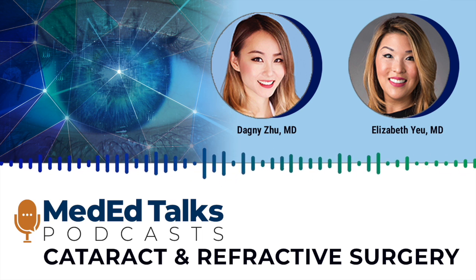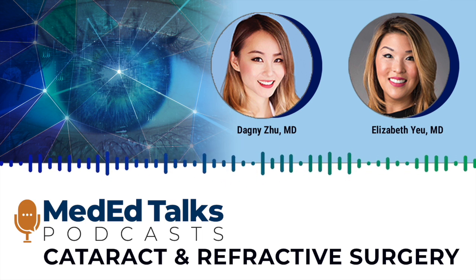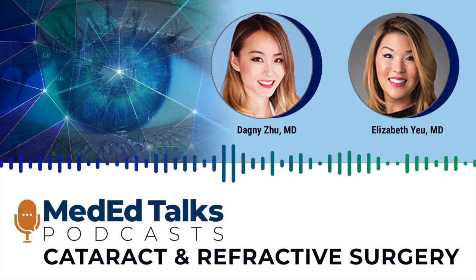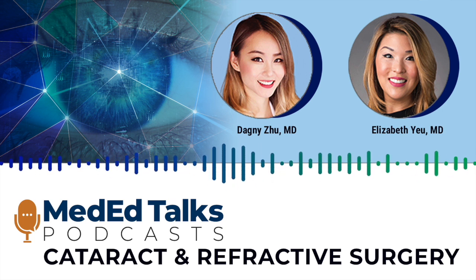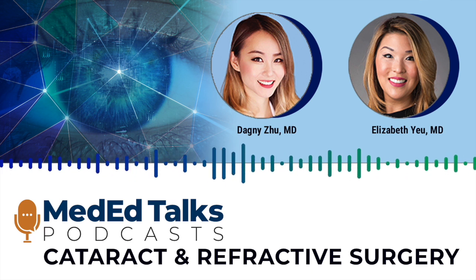We've come a long way not only in terms of efficiency but in maximizing the patient's experience. My myopes with long eyes and deep chambers get a lot of bouncing that causes stretching of the ciliary nerves, so they really benefit from anterior chamber stability. Patients with pseudo-exfoliation and loose zonules also benefit — you want to maintain that pressure so you don't have vitreous coming forward. We've done a lot to address post-occlusion surge. Some of the less fancy changes that have improved that include changes to the tubing — the less compliant and more rigid the tubing, the smaller the diameter, the less likely you are to have post-occlusion surge.